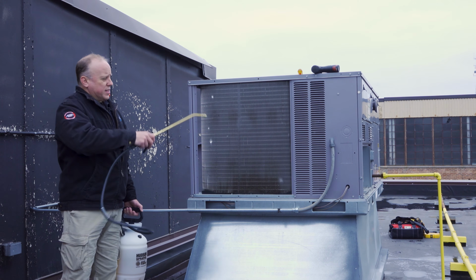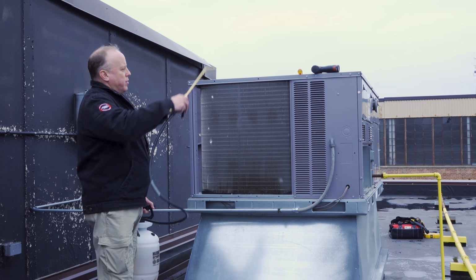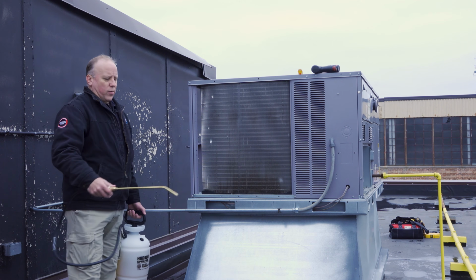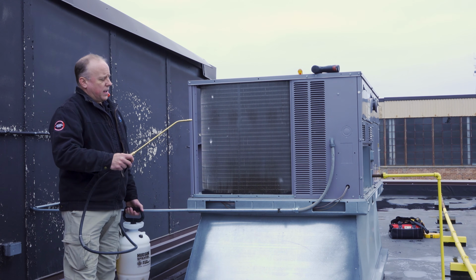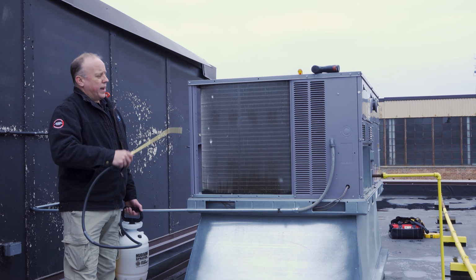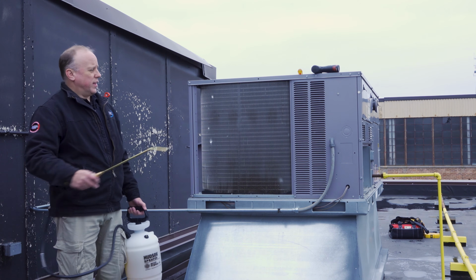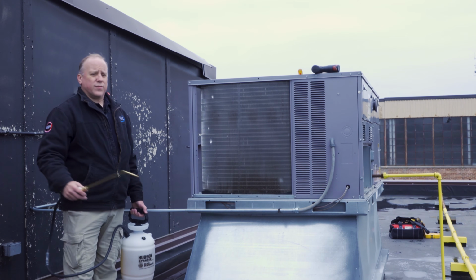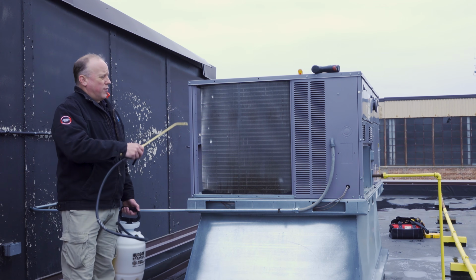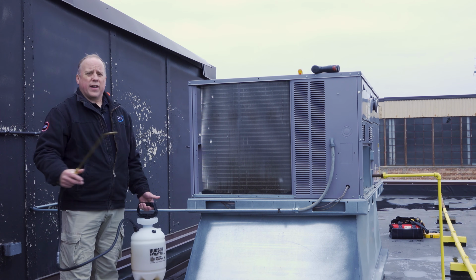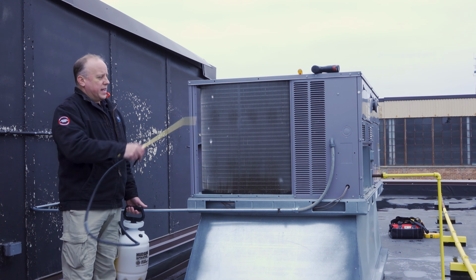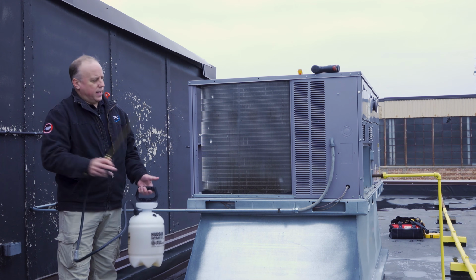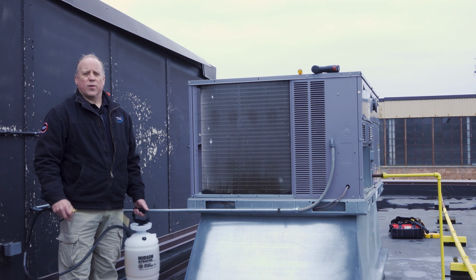I'm just going to spray this down, then we're going to open up the unit from the top because we are going to rinse it from the inside out. Depending on how dirty the coil is, if it's really dirty you could get the cleaner on both sides. If you have a foaming cleaner, it will actually push stuff out of the coil, so you can do it from the inside or the outside, and it'll push stuff out of the inside of the coil too.